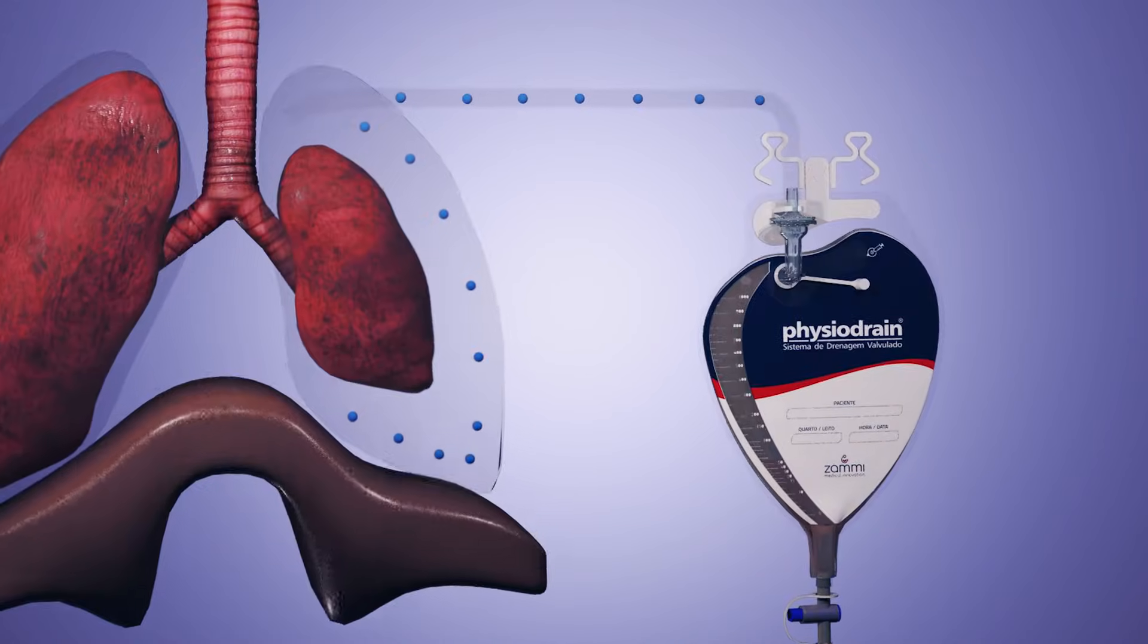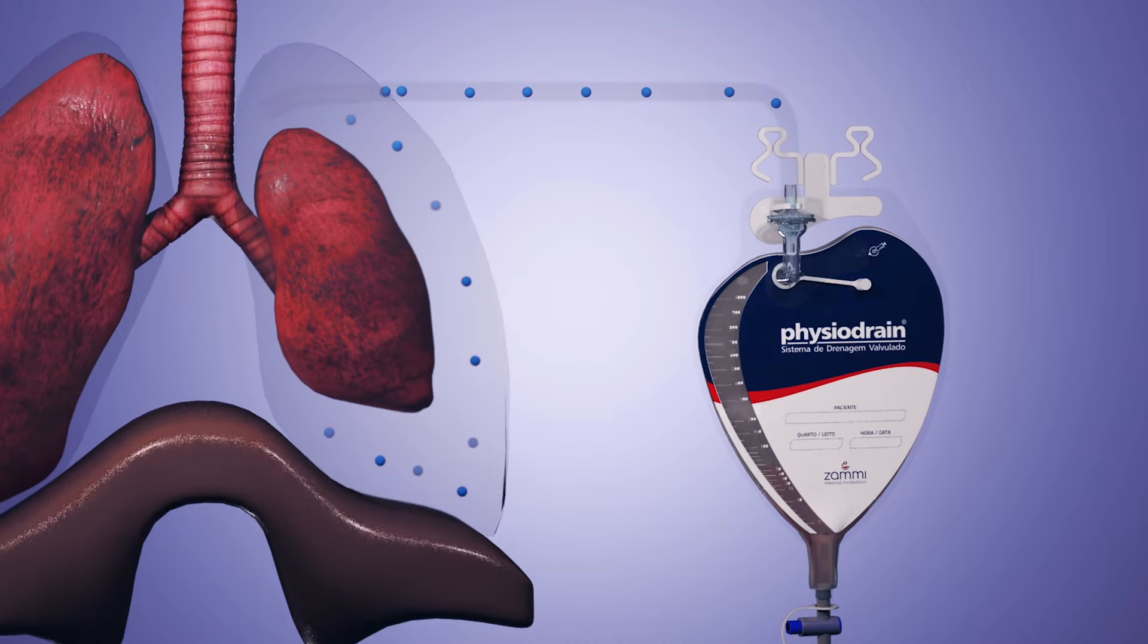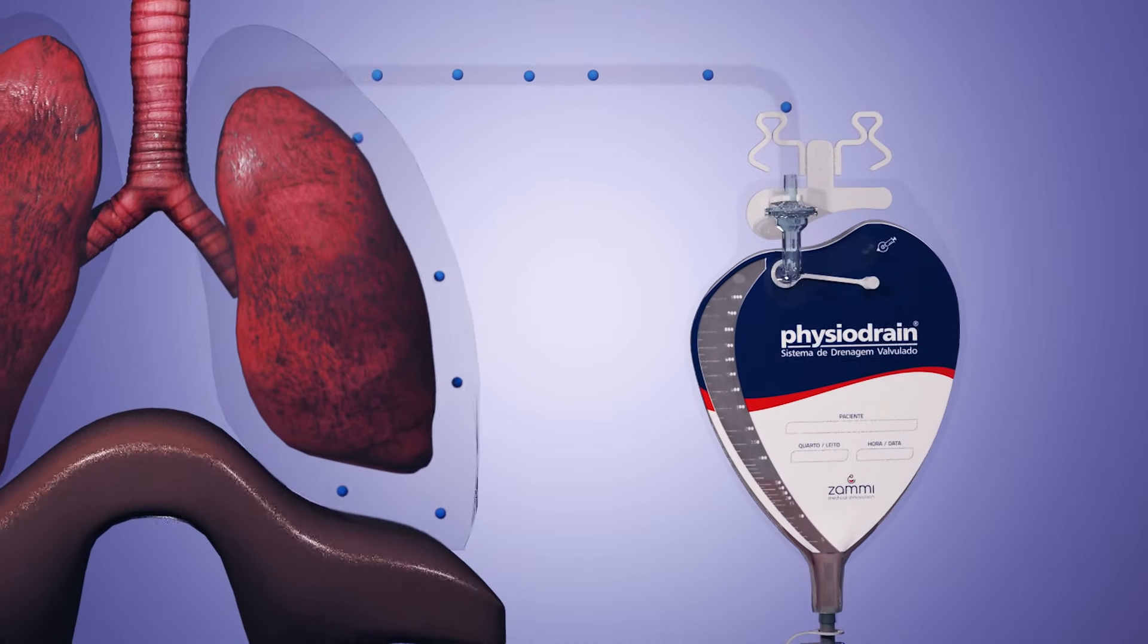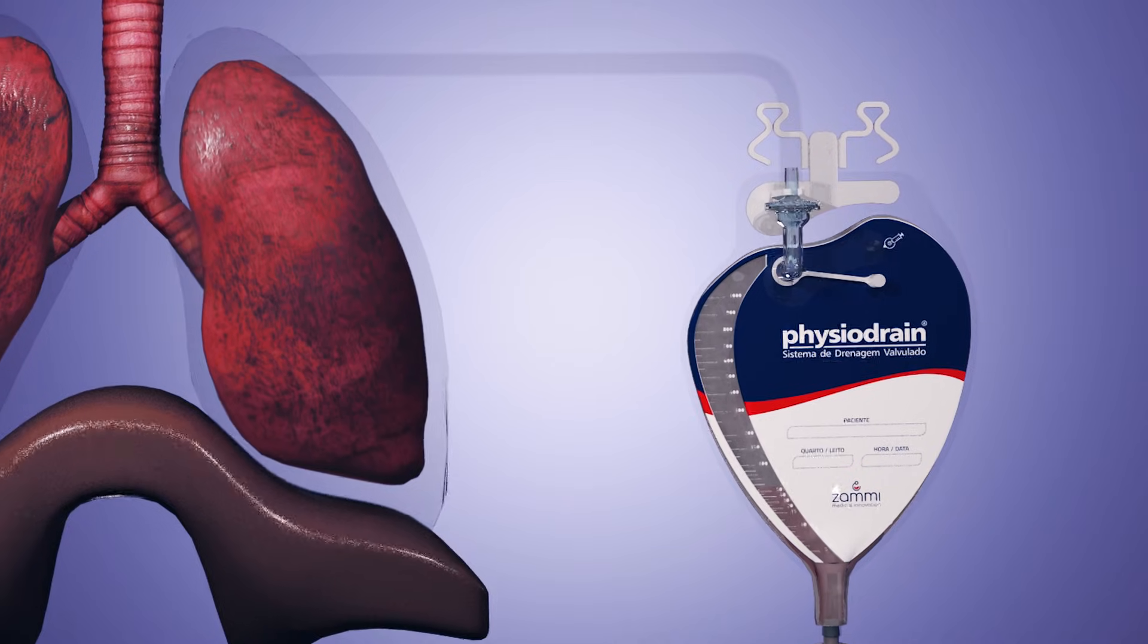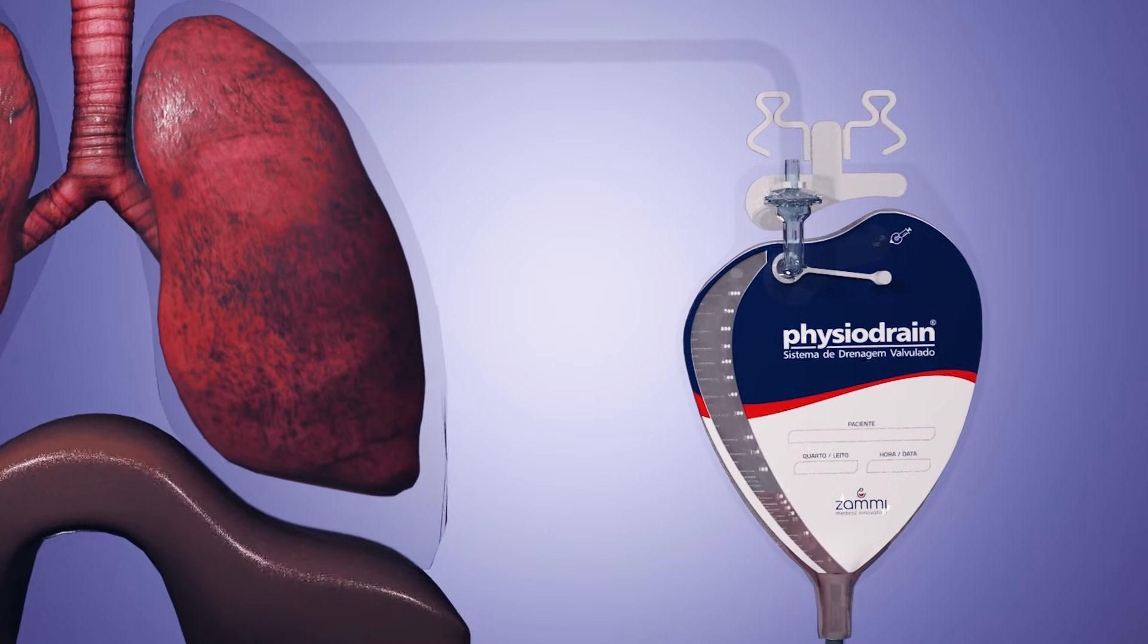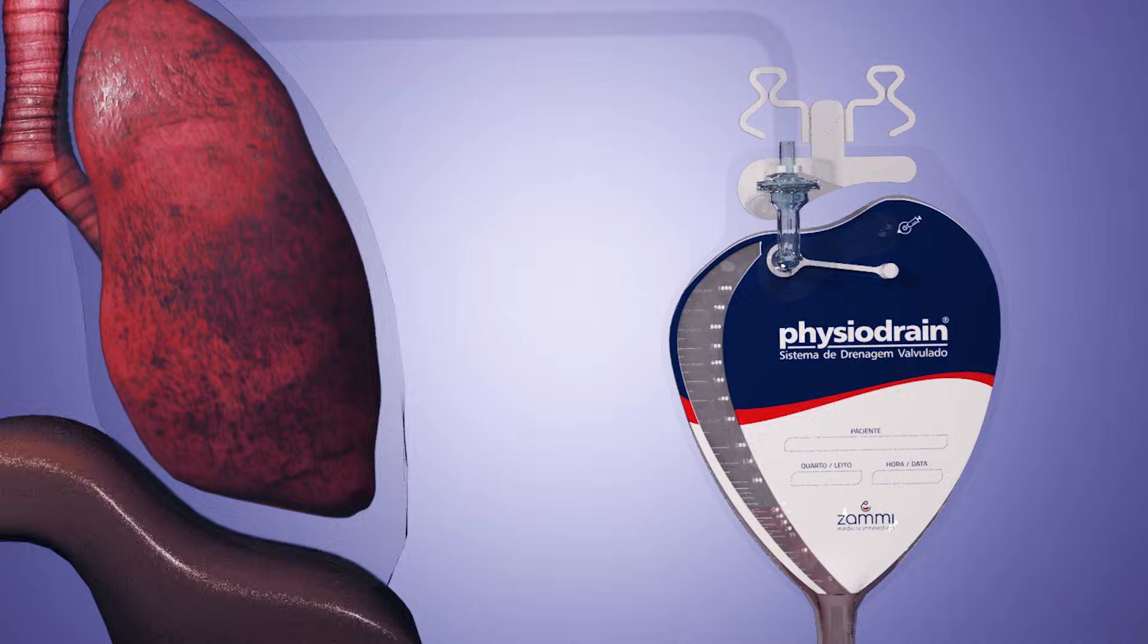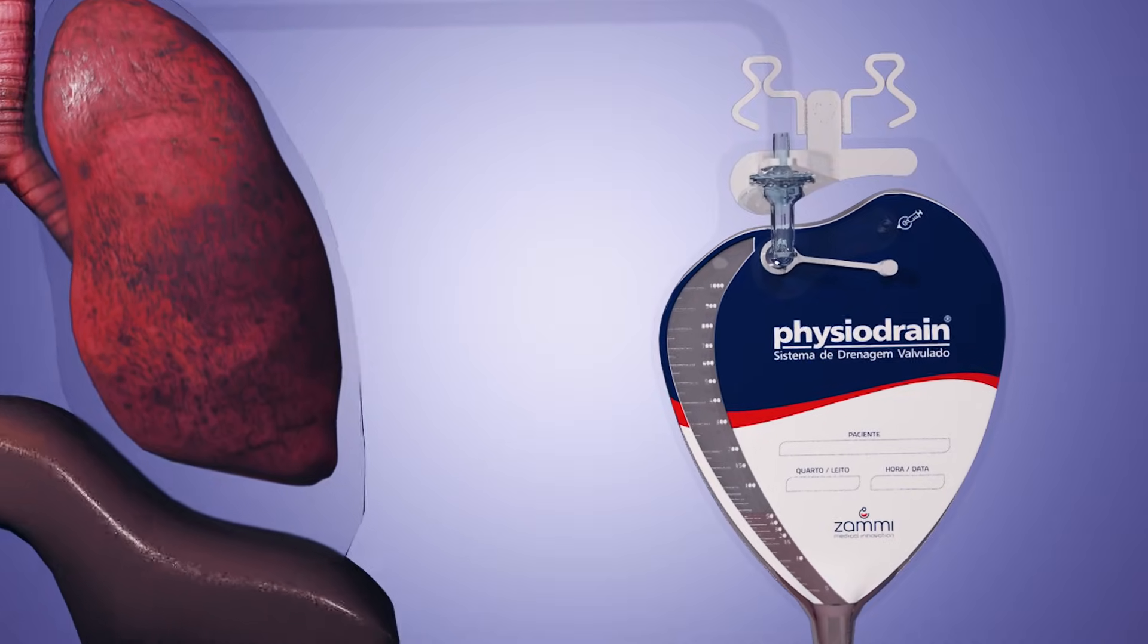The physiodrain system has an opening pressure very near to zero and there is no backflow. Any upward movement of the diaphragm provokes drainage and any downward movement expands the lung. Drainage is faster and more efficient, allowing full lung expansion in less time.